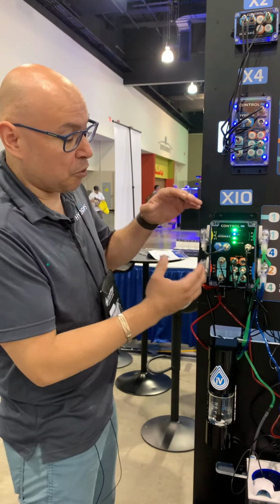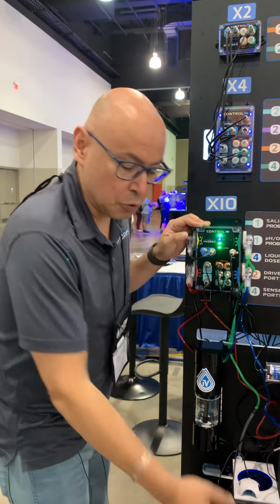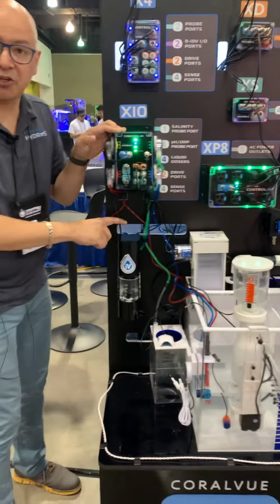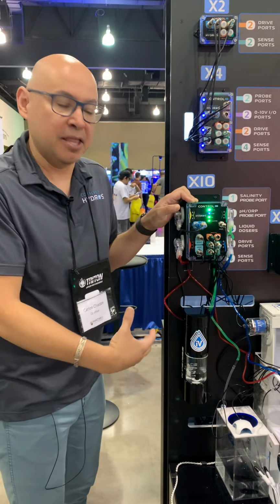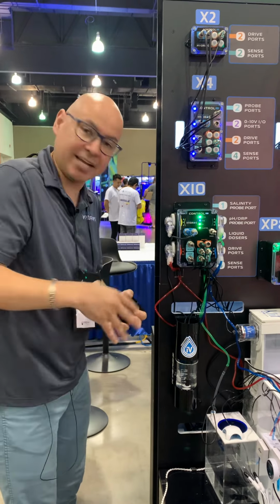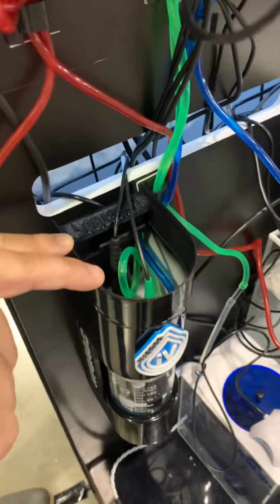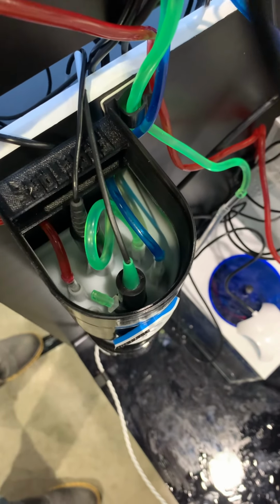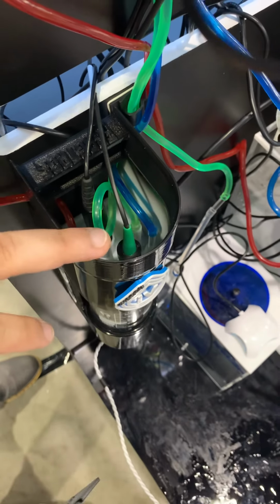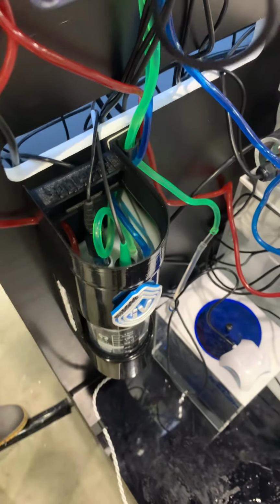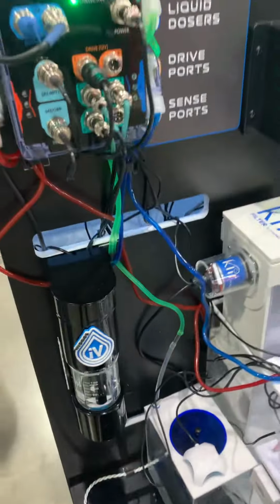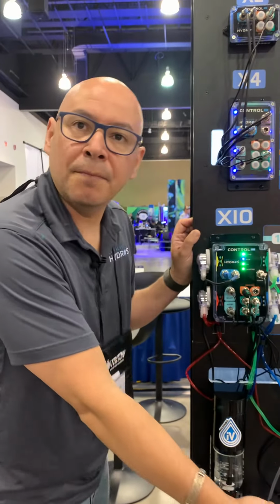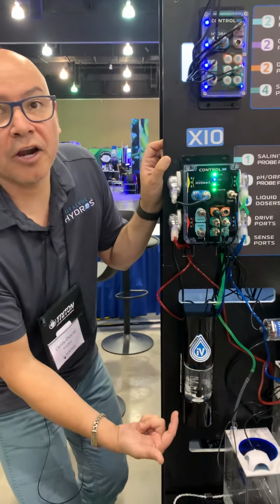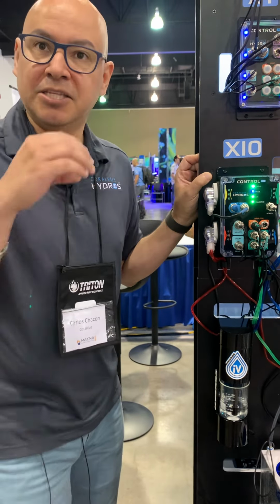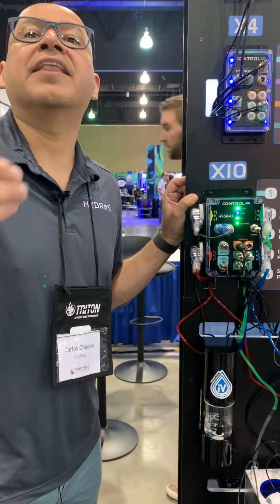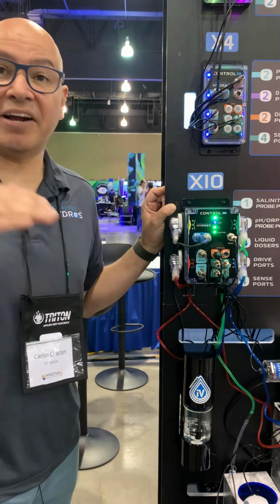So we're giving you the option to have salinity, and yes, you can put it inside the sump. But if you decide to get the IV, which is an accessory, it facilitates putting in the conductivity probe. Take a look at this right here. You can see there's a conductivity probe and a pH probe there. It allows you to put the conductivity probe into an isolated device. Then you can create a schedule that tells the Hydros, every 2 hours, pull water from the sump, bring it into this isolated device, stir the water so the bubbles are gone, stop the magnet so there's no electric interference, and then take the reading. So now you have a clean reading.